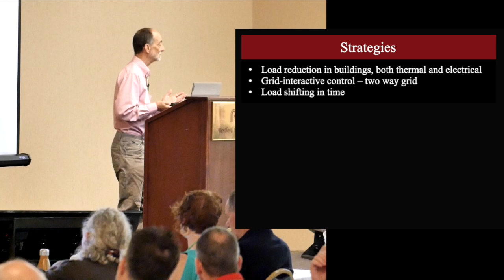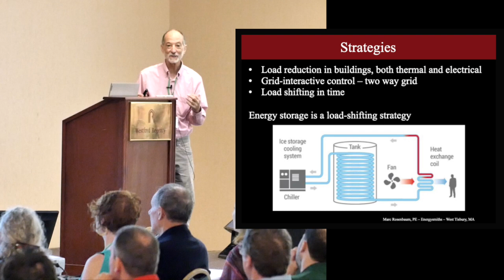Here's a classic energy storage load shift: ice storage. You get an ice-making chiller and tanks, and make ice. Traditionally this is done at night, when the grid baseload energy is cheap, so it's really an economic shifting strategy, but we can also use it to peak shave. That's a very classic way to shift load.